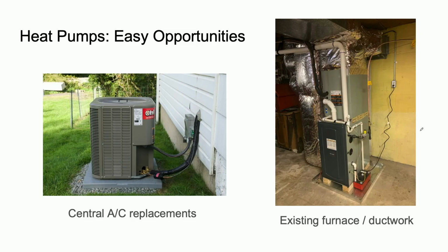Yeah, so the caveat, the asterisk for putting a heat pump into an existing furnace, a couple of things. So that ductwork in the basement better be insulated because if you're going to be running cold air through that, you're just asking for condensation and rust and leaks and all that. So definitely someone's going to need to insulate the ductwork in the basement. And the other thing is this furnace ductwork here is designed to deliver a lot of BTU heating capacity from a furnace. It's not really designed for a much lower BTU heat pump. It's not ideal. If you were putting in ductwork just for a heat pump, it wouldn't look like this size, but it can be used. Okay.